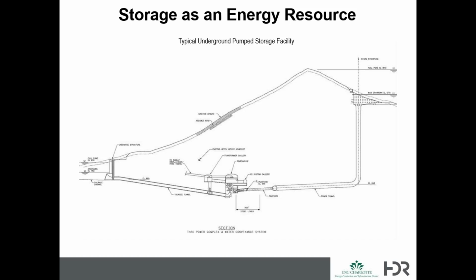The center line of the pumps has to be about 10% of the total head below the lower water level. There has to be about 10% of that elevation difference of submergence. So if it's 1,200 feet total head difference, then the center line of the pumps has to be about 120 feet below the minimum level of Lake Jocassee. You don't want to starve the machines of water. You've got to prime the pump.